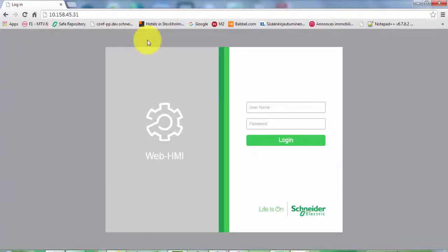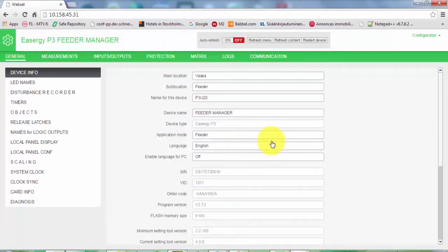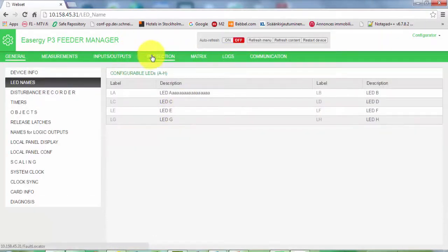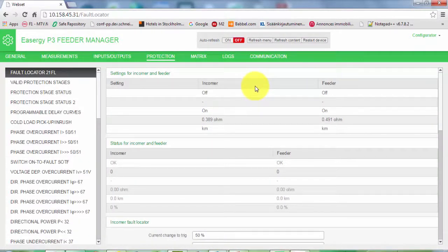Once you have activated the HTTP server and you know the IP address, simply open your browser and directly write the IP address. The device will answer with a login screen and you have to know the username. For the configurator level, the username is 'CONF' and the password is '2'. After accepted login, the device will answer with the available menus and you can check protection setting changes and other changes, almost the same way as using Easergy Pro.